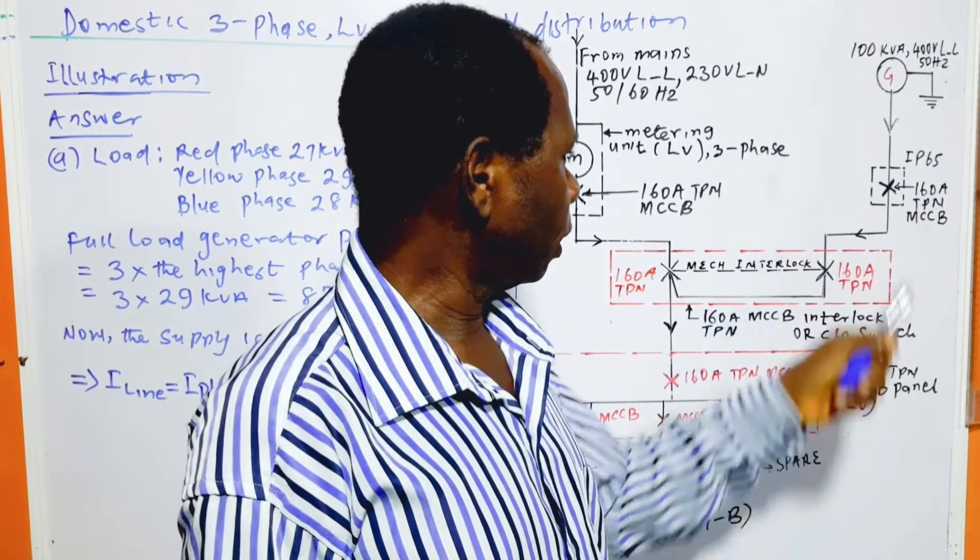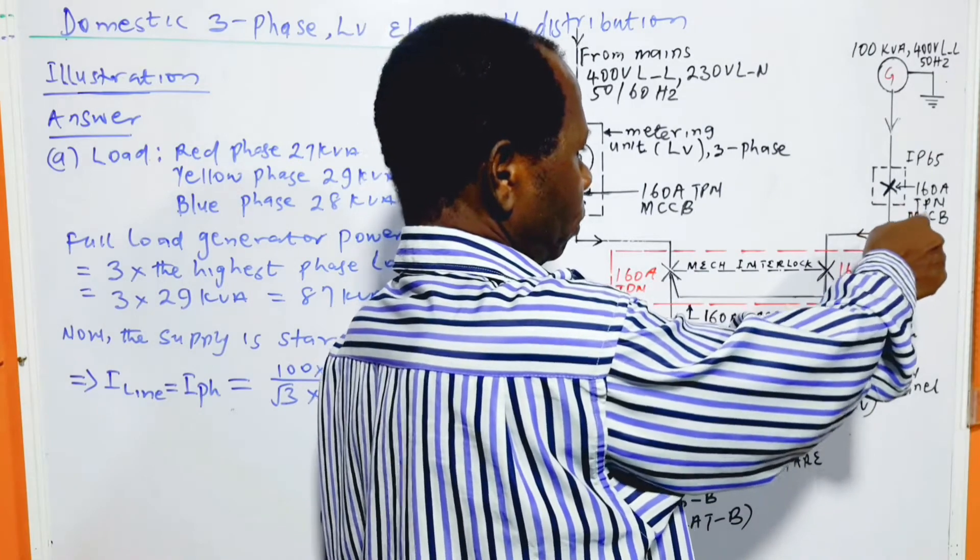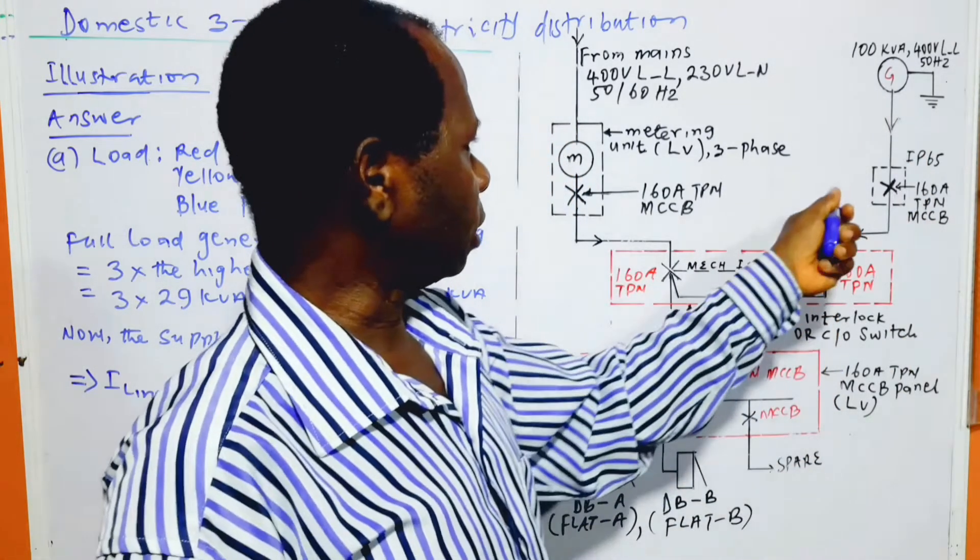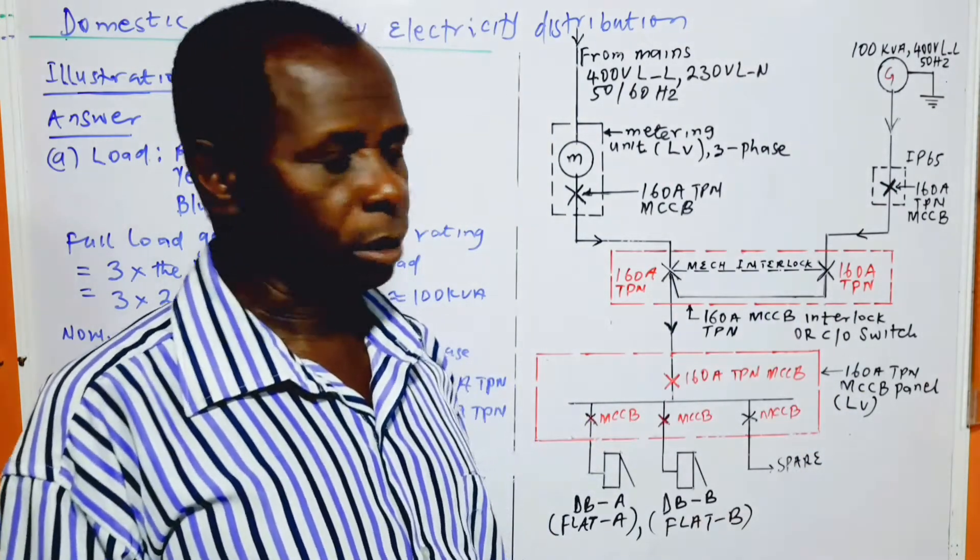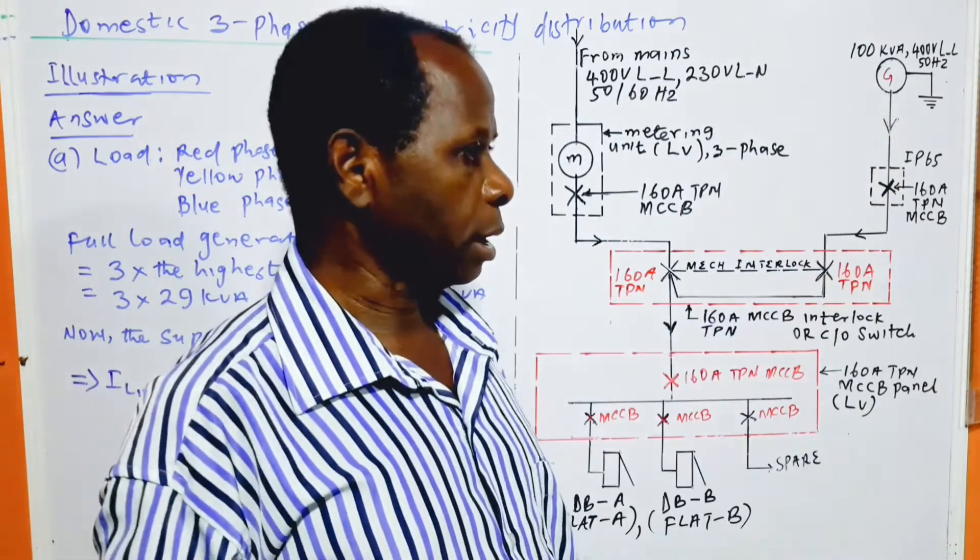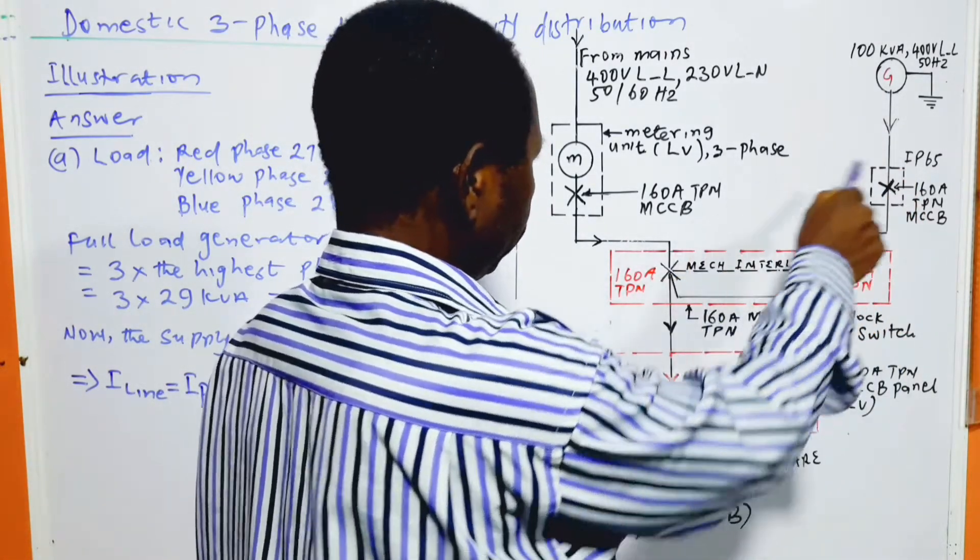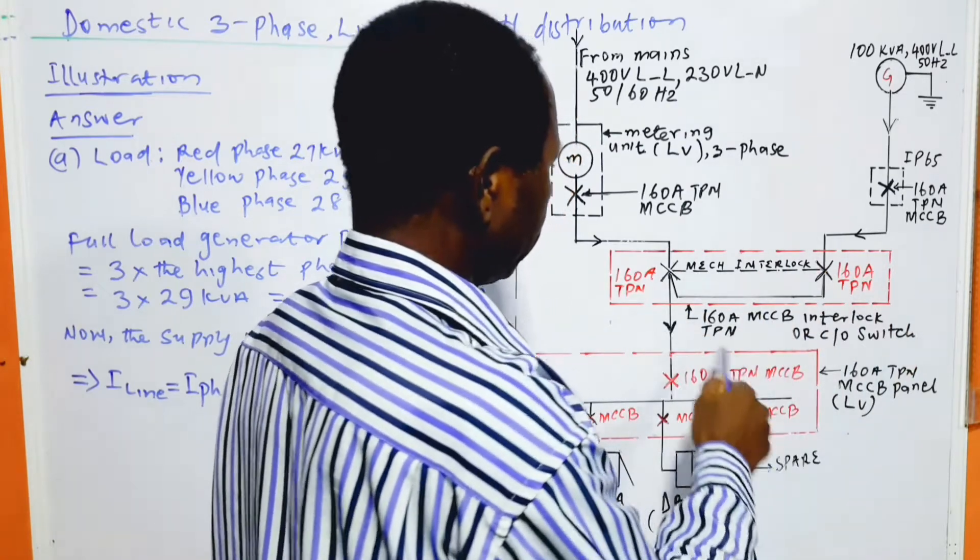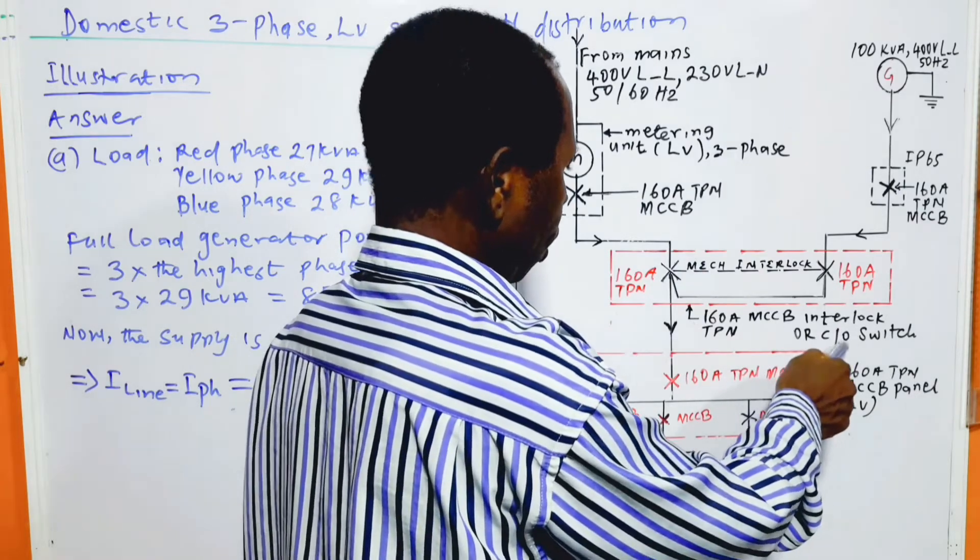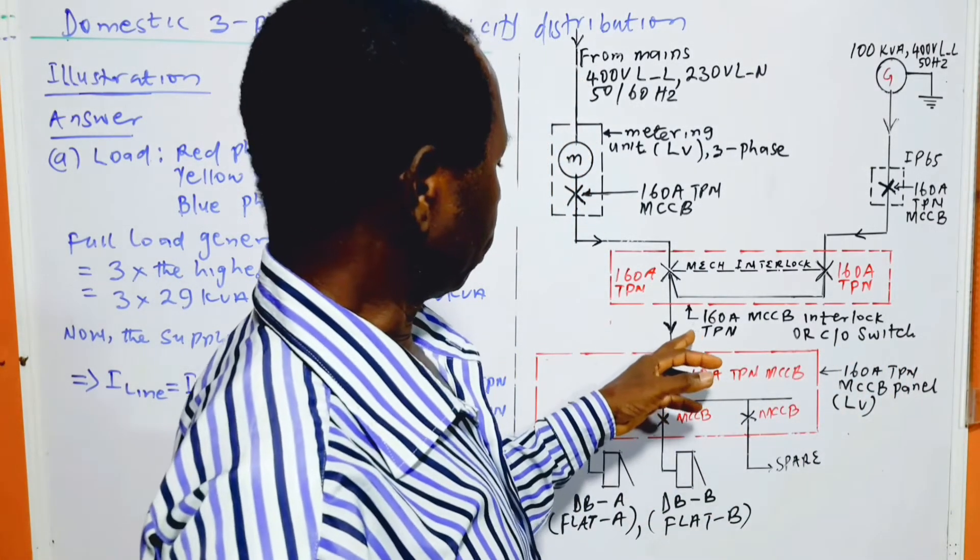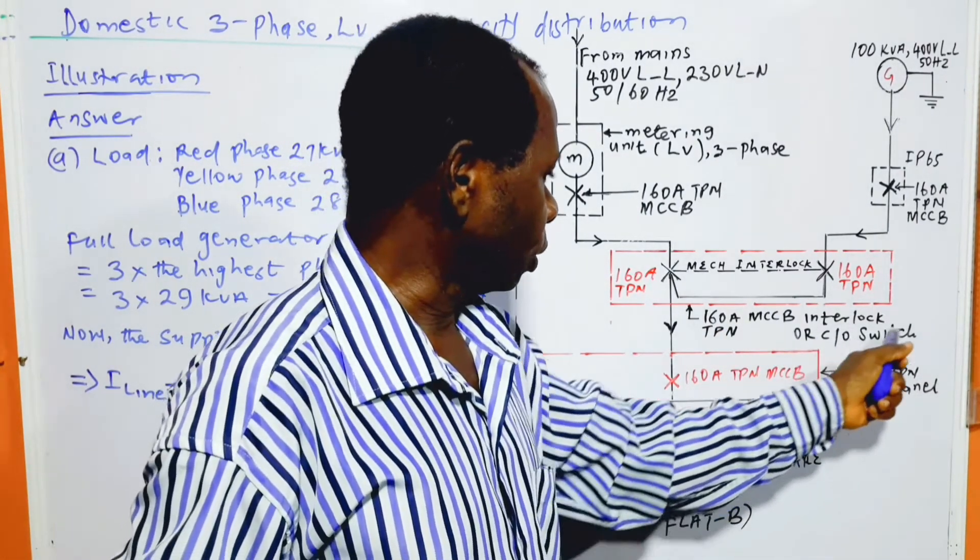From here we have ingress protection IP65 cubicle type MCCB to further protect the generator. We know that the generator itself has an inbuilt circuit breaker. This one is just to complement the inbuilt circuit breaker. Then from here we come to this red box, which is 160 amp MCCB interlock or changeover switch, 160 amp MCCB triple phase with neutral interlock or changeover switch.